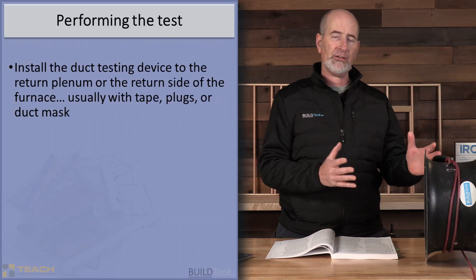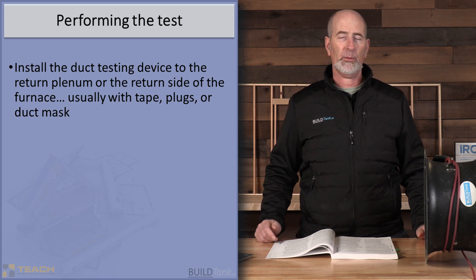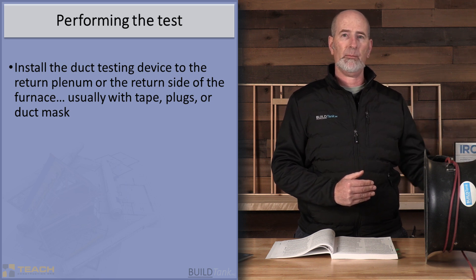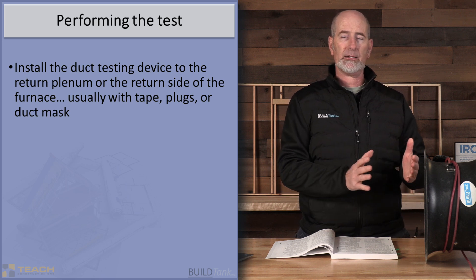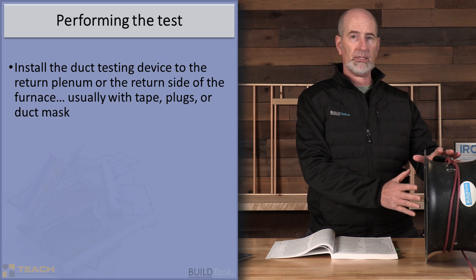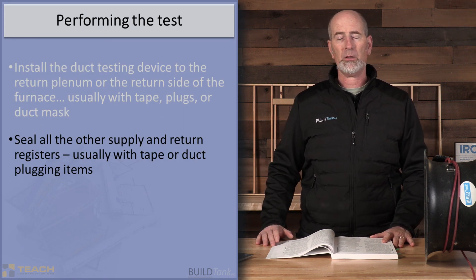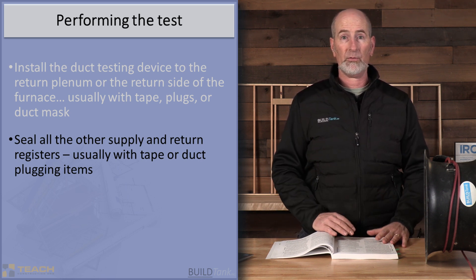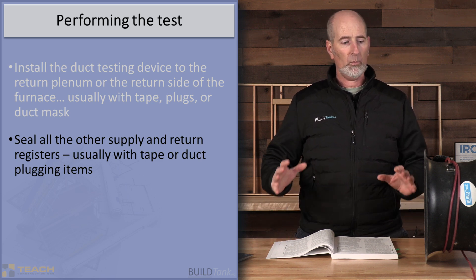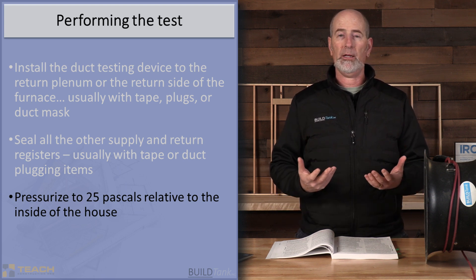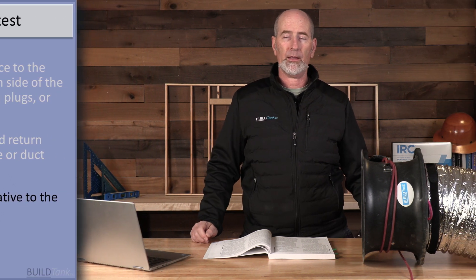When we're doing this total duct leakage test, we put a duct testing device like this one and attach it to the return side of the duct system. The return side can be either at a large enough return that has access to the furnace cabinet — where the furnace blower is located — or it can be connected directly at the furnace cabinet at the blower chamber itself. Once connected, we then go around the house and block off all the supply and return openings, taping them off at the surface where they penetrate through the drywall or subfloor, sealing off at that location.